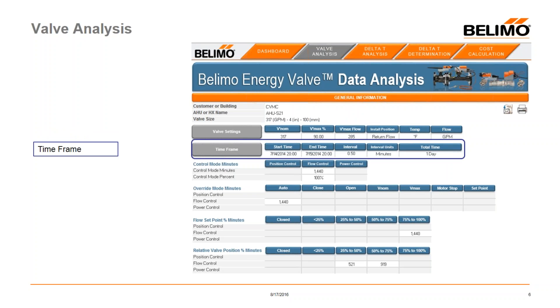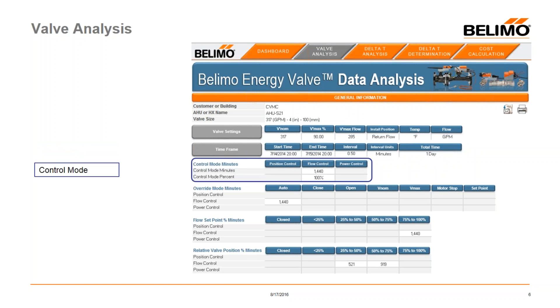The time frame box reminds you what you selected on the dashboard screen. For instance, if you imported 31 days of data but then selected down to one day, all calculations throughout the tool will reflect one day. The control mode box tells you how many minutes by mode the valve is operating — in this scenario the valve was in flow control for 1,440 minutes, which is 100% of the time.